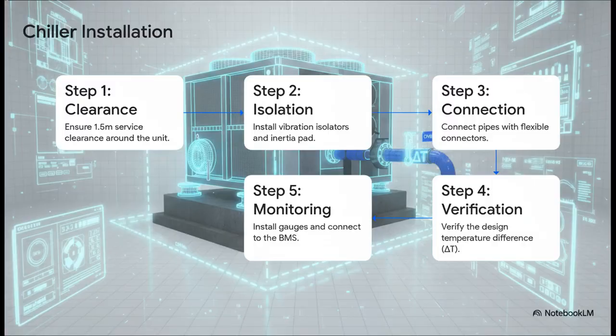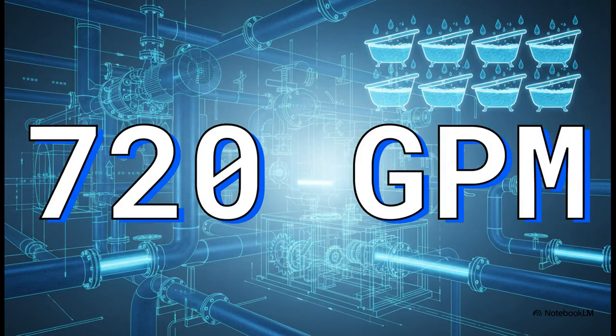There's no other way. So you run the math for a pretty standard 300-ton system, and what do you get? You get this number, 720 gallons per minute. Let me put that in perspective for you. That's like filling up 14 bathtubs with water every single minute. That's the sheer volume of water this machine is constantly circulating. It just shows you the incredible scale of the energy that we're moving around.